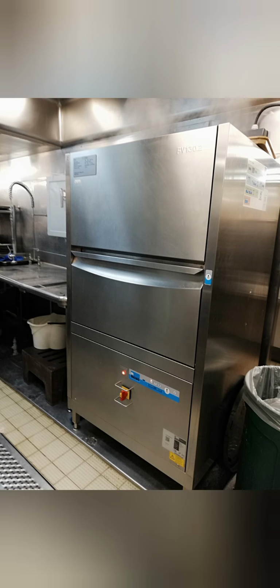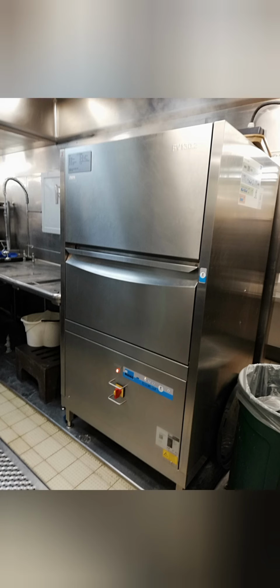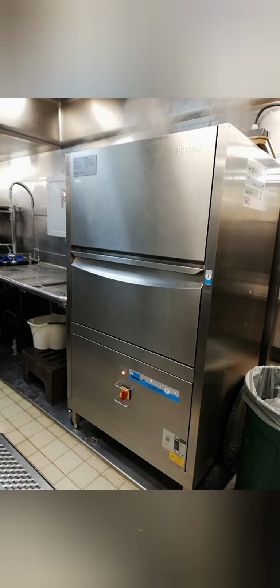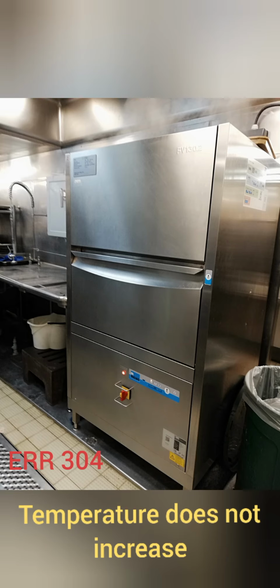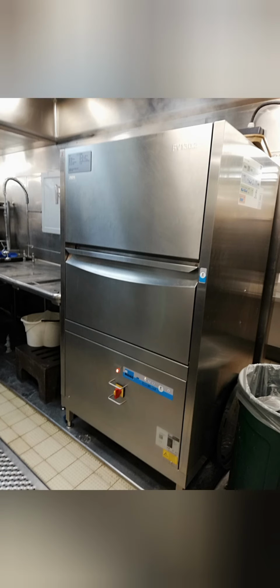Recently I had these errors, 204 and 304. And what are these errors? Error 304: temperature does not increase, whilst error 204 is: following the end of the rinse time, still no change detected at the level switch. So of course, if you have a manual, you can check the description of errors and their remedy.